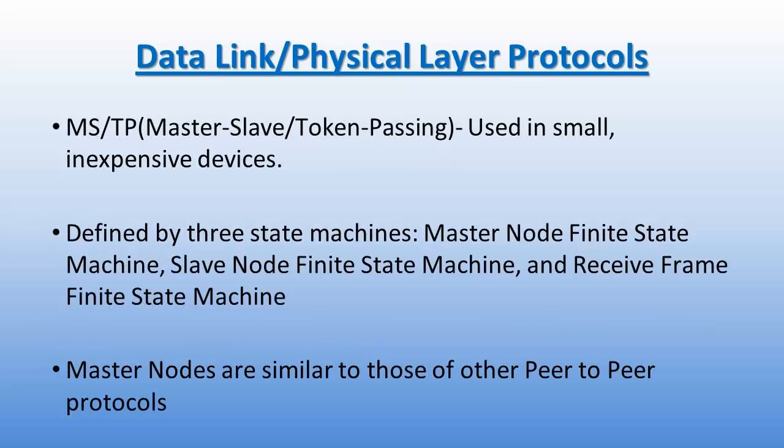BACnet MSTP is a data link protocol unique to BACnet, commonly used as a field bus. The acronym MSTP stands for Master Slave Token Passing. This protocol uses EIA-485 as the physical layer and is defined using three state machines: Master Node Finite State Machine, Slave Node Finite State Machine, and Receive Frame Finite State Machine.